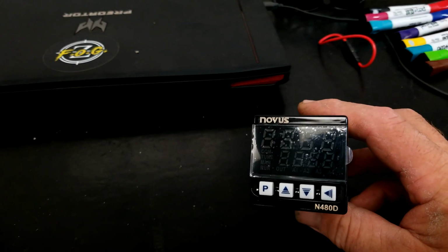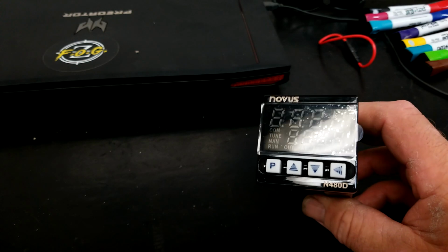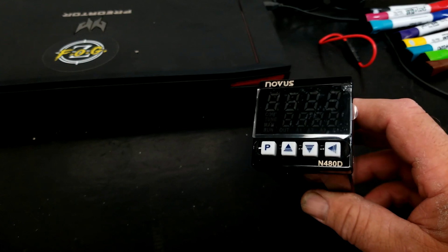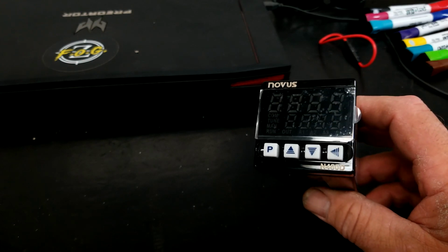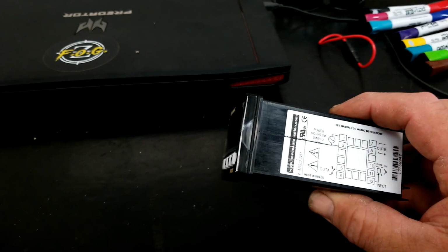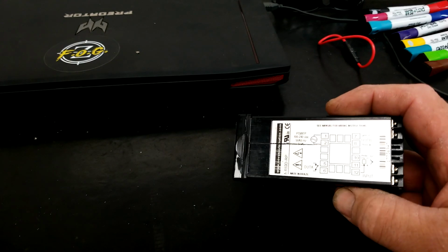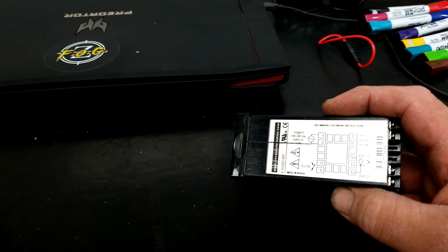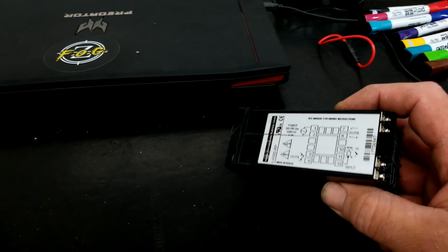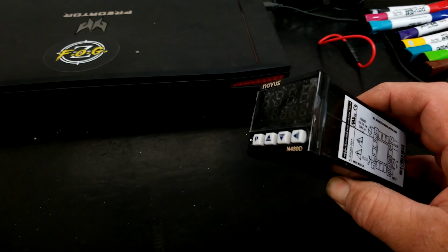Next up is a Novus 480D. These are the controllers I've been using, and I recommend them, but you can run any controller you want. If you do, you need to check with your paperwork. There's a wiring diagram on the side, and we're going to be wiring this example to this diagram. Okay, so that's a temperature controller. It goes in the face of your control box.